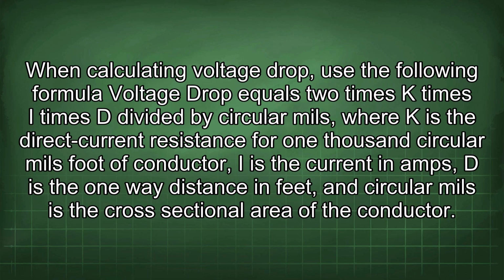When calculating voltage drop, use the following formula: voltage drop equals 2 times K times I times D, divided by circular mils, where K is the direct current resistance for 1000 circular mils per foot of conductor, I is the current in amps, D is the one-way distance in feet, and circular mils is the cross-sectional area of the conductor.